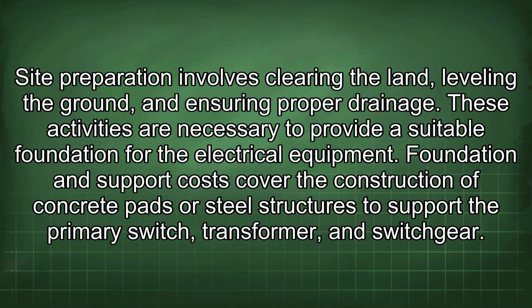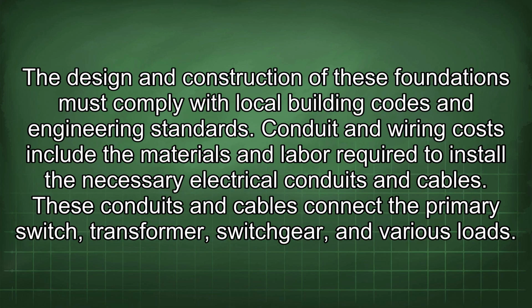Foundation and support costs cover the construction of concrete pads or steel structures to support the primary switch, transformer, and switchgear. The design and construction of these foundations must comply with local building codes and engineering standards. Conduit and wiring costs include the materials and labor required to install the necessary electrical conduits and cables. These conduits and cables connect the primary switch, transformer, switchgear, and various loads.